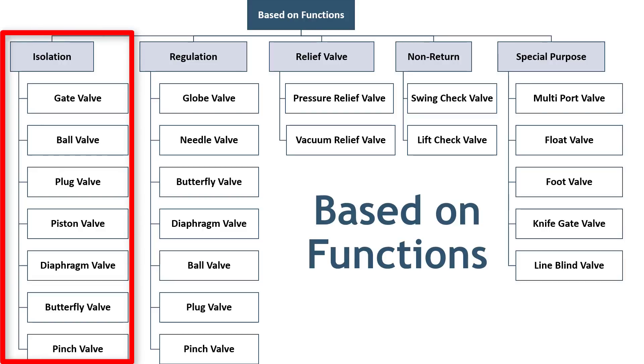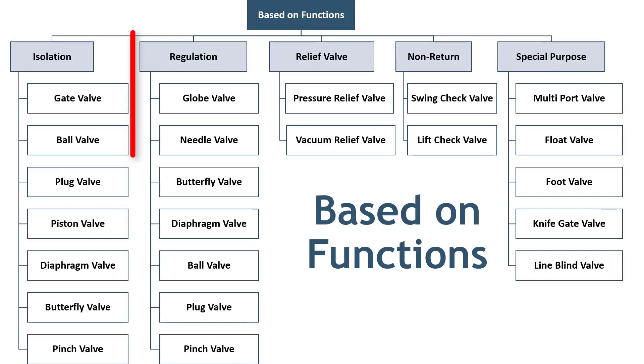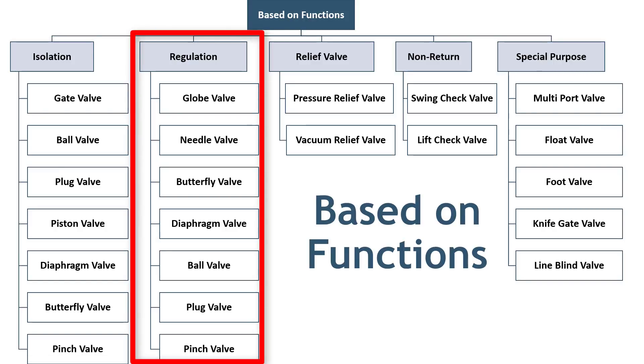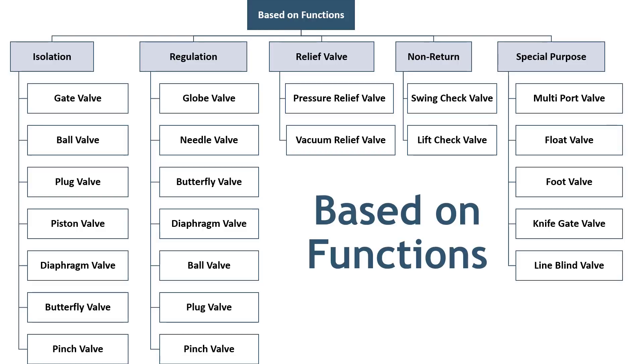The isolation valves isolate or cut the supply of fluid when needed. A control valve that regulates the flow of fluid falls in the regulation category. Globe, needle, butterfly, diaphragm, ball, plug, and pinch valves are used as control valves. Some valves have a dual purpose — such as globe and ball valves — and can be used as both isolation and control valves.